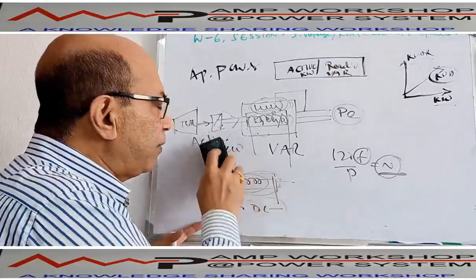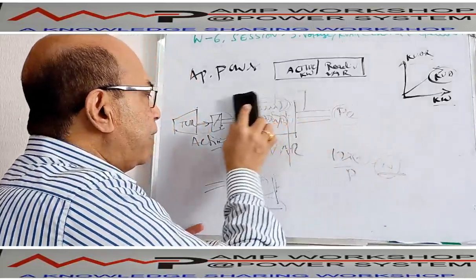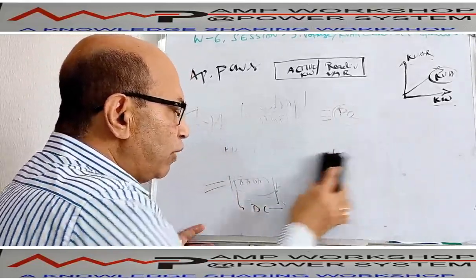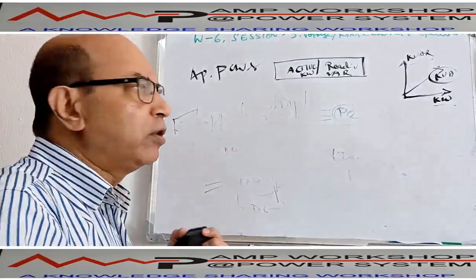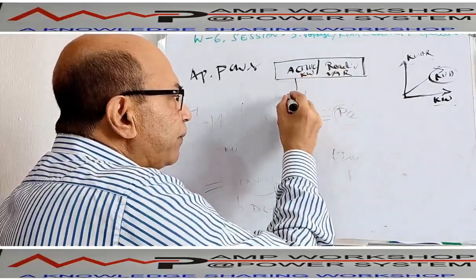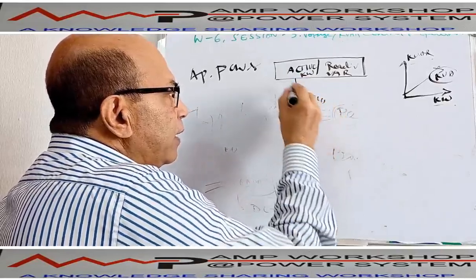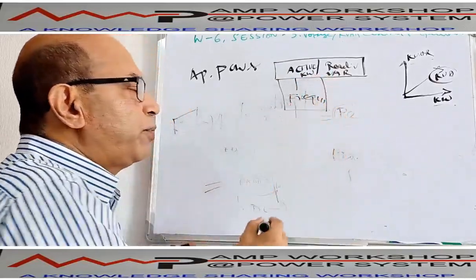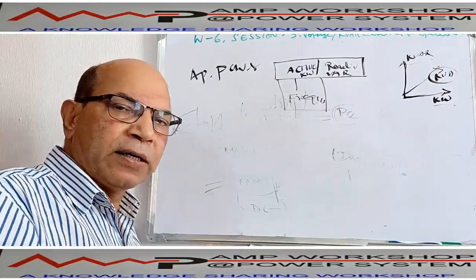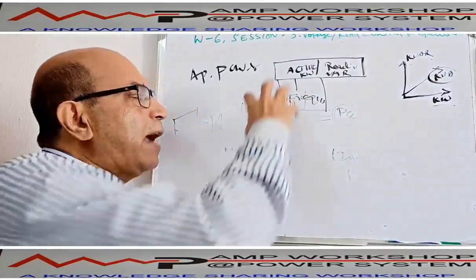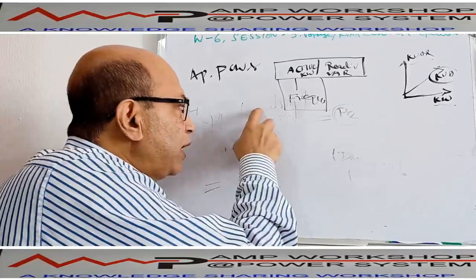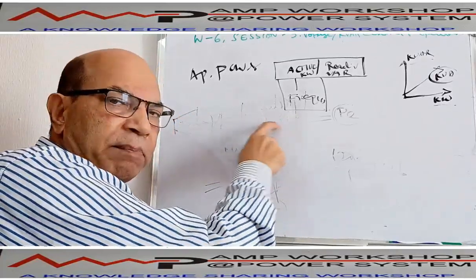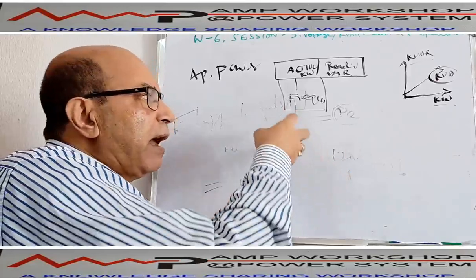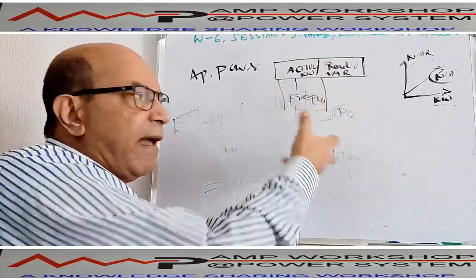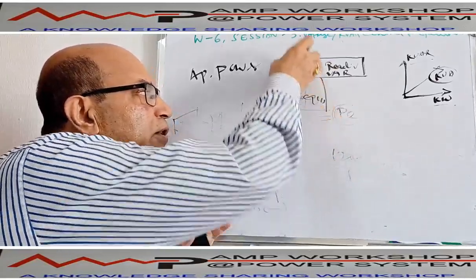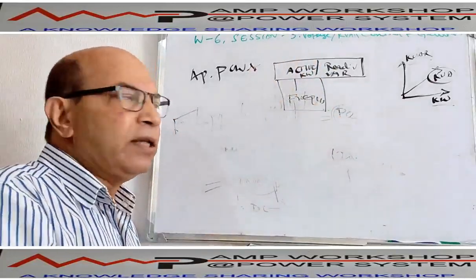That means, in another way, the active power: when the turbine is rotating, it is producing active power, and that active power is responsible for producing the frequency. In other words, if we want to control the frequency, we have to control the active power, or if we control the frequency, then the active power will change. If we reduce the frequency, immediately the active power or rotational speed will drop, and then the amount of power produced by the machine will change. So the active power and frequency are correlated; they complement each other, they are replicas.